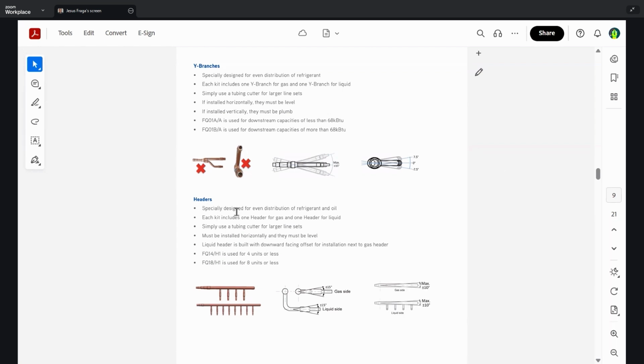So moving on to headers, they are specifically designed for even distribution of refrigerant and oil. Each kit includes one header for gas and one header for liquid. And same thing as the Y branches, simply use a tubing cutter for larger line sets. They must be installed horizontally and they must be level.